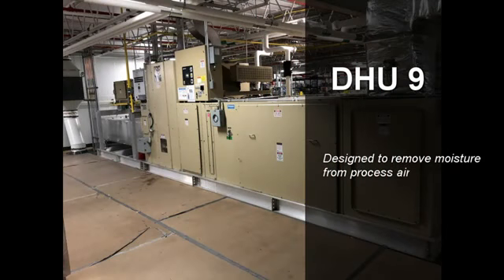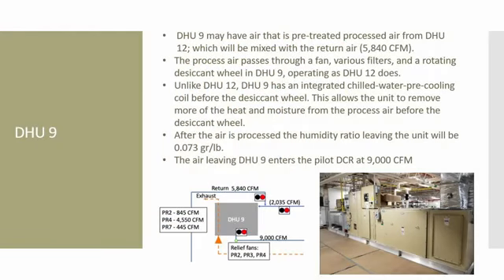Regardless of if the air moves through DHU12 or not, all of the process air then moves through DHU9, which further removes moisture from the process air. This air is mixed with 5,840 CFM of return air from the pilot dry clean room. The process air then passes through a fan, various filters, and a rotating desiccant wheel in DHU9, which operates just as DHU12. Unlike DHU12, though, DHU9 has an integrated chilled water pre-cooling coil before the desiccant wheel. This allows the unit to remove more of the heat and moisture from the process air before entering the desiccant wheel. The humidity ratio leaving the unit after processing will be 0.073 grains per pound, which then enters the mixing plenum and the pilot dry clean room at 9,000 CFM.